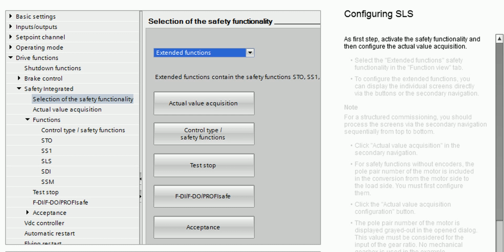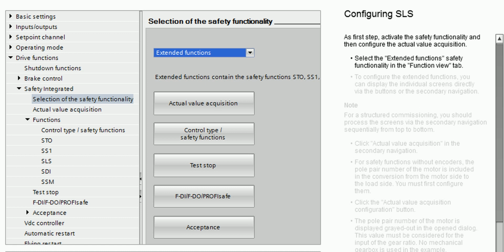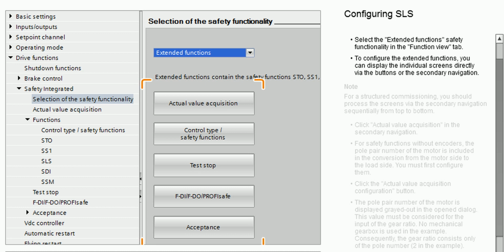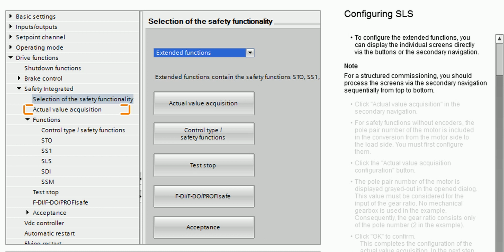As first step, activate the safety functionality and then configure the actual value acquisition. Select the Extended Functions, Safety functionality in the Function View tab. To configure the extended functions, you can display the individual screens directly via the buttons or the secondary navigation. Note: for a structured commissioning, you should process the screens via the secondary navigation sequentially from top to bottom. Click Actual Value Acquisition in the secondary navigation.